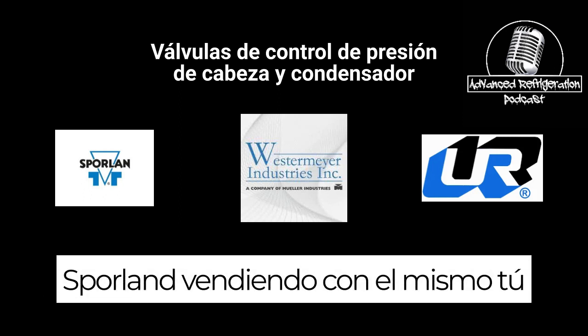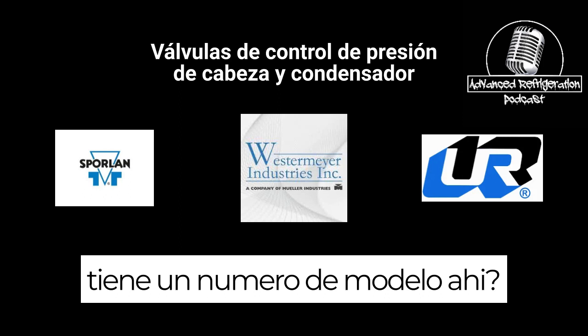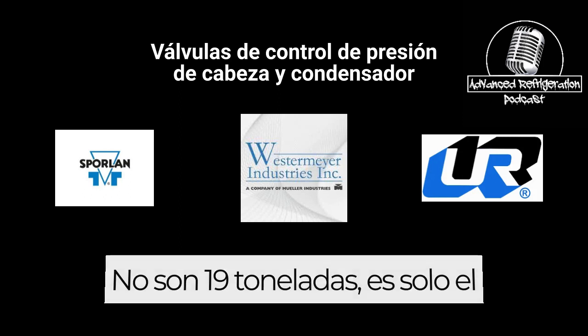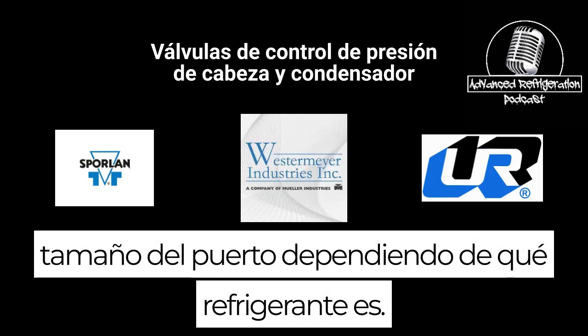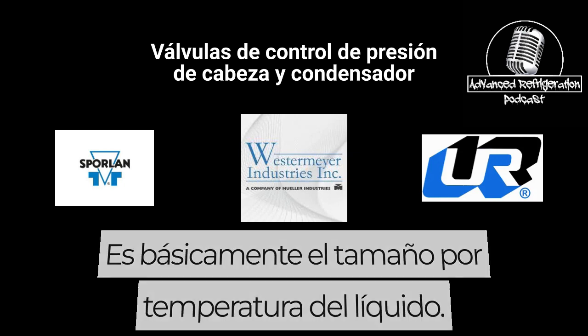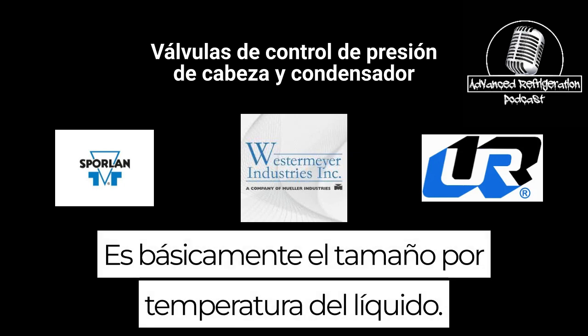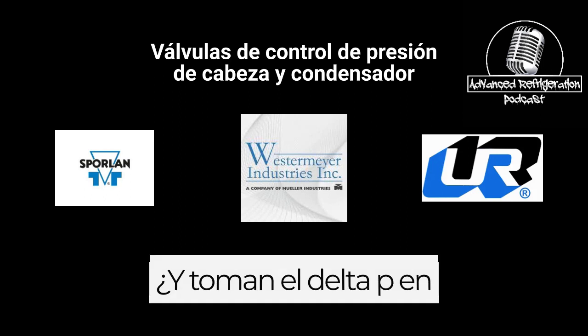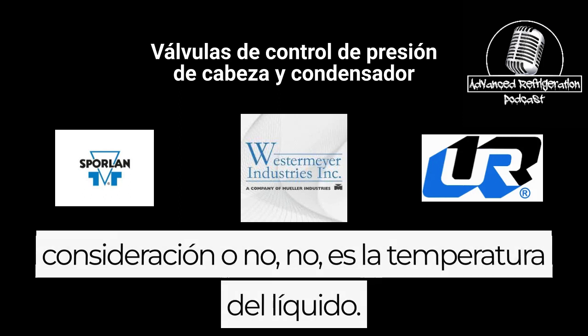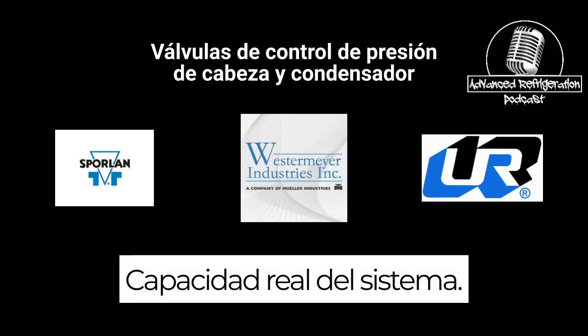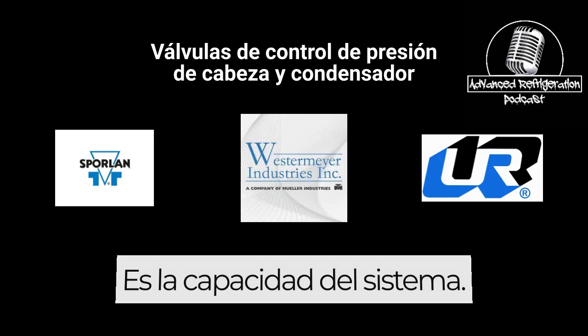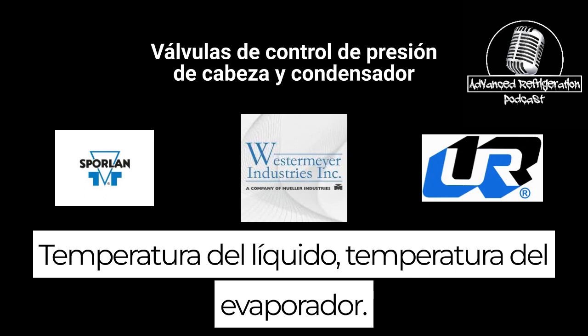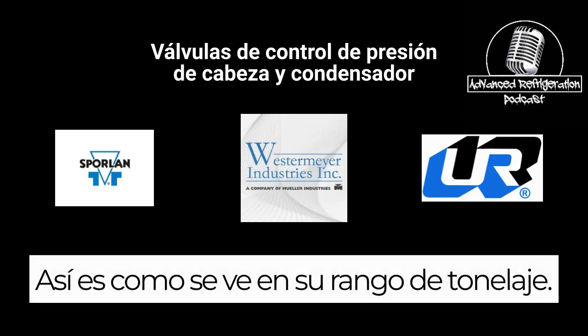Sporlan sells them the same way. You have a model number on there, ME 19. It's not 19 tons. It's just the port size, depending on what refrigerant it is. Same thing with the holdback valve. It's basically sized per liquid temperature. Liquid temperature, and do they take the delta P into consideration or no? No, it's liquid temperature, actual system capacity. Yeah, it's system capacity, liquid temperature, and evaporator temperature. That's how it's looking at its tonnage range.